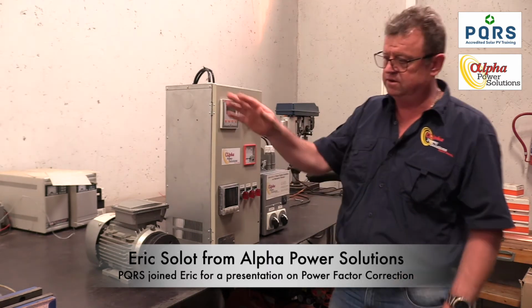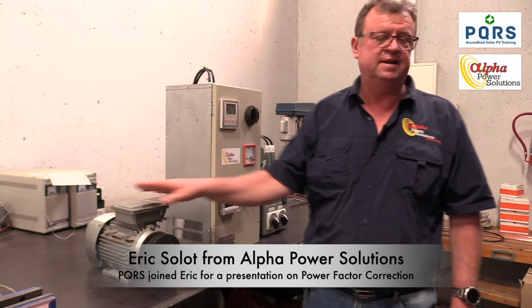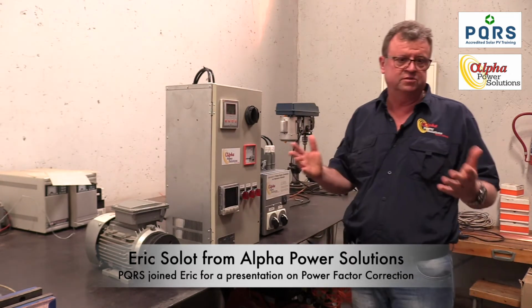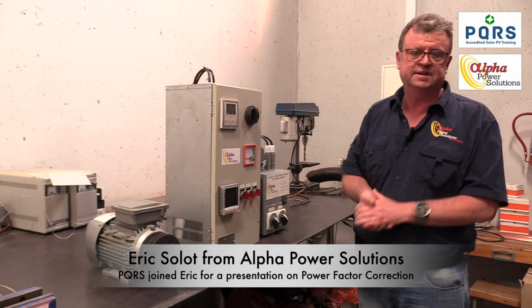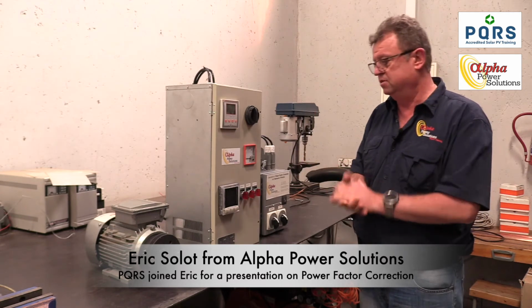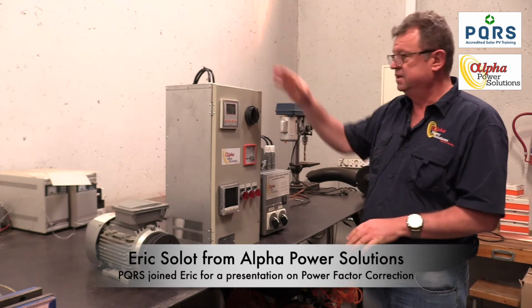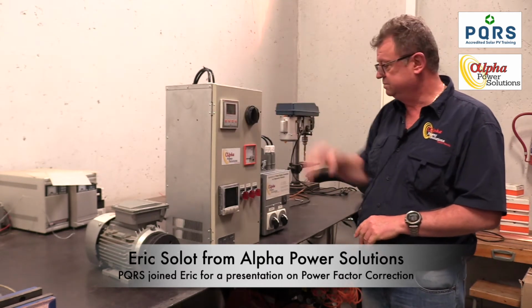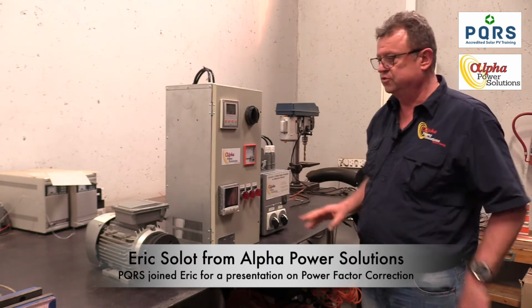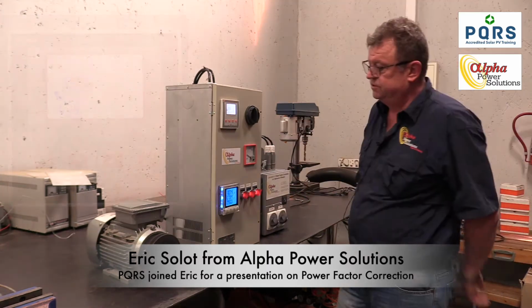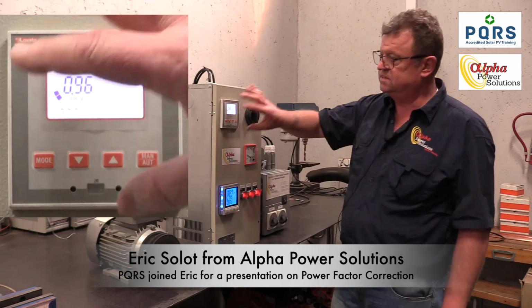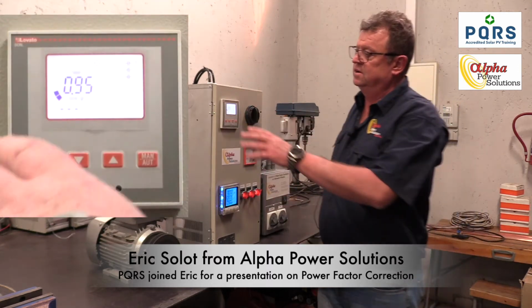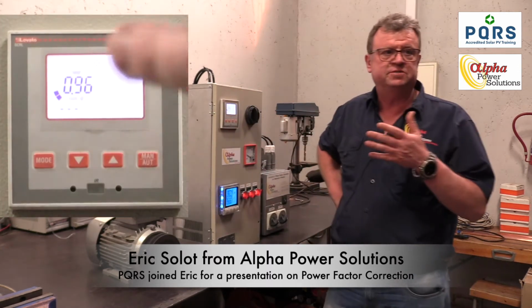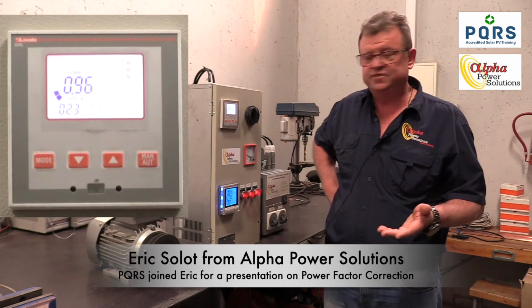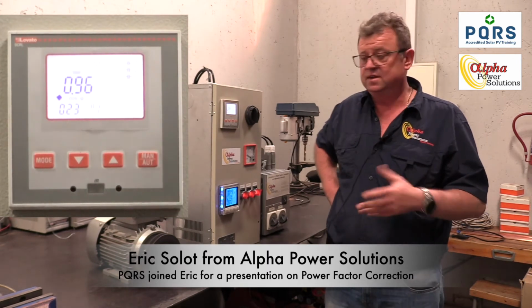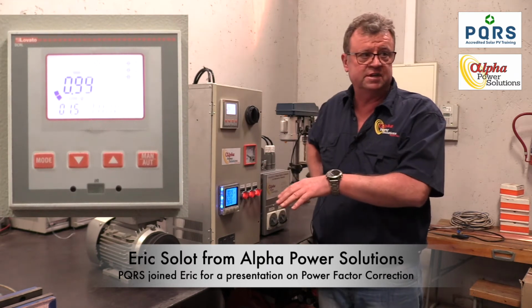So we have here a motor that will simulate the inductive load that would be present in a factory or commercial building. We have a power factor correction panel here, and this is just a little control box to manage this whole thing. So basically what you have here, this is the actual brain. This device is fed with a current feedback and a voltage feedback, and allows it to calculate what the power factor of the load is.